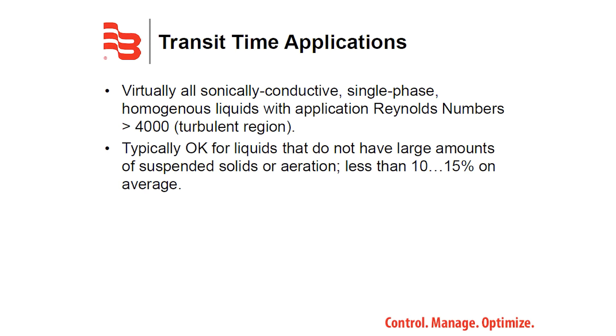Transit time applications require Reynolds numbers greater than 4,000. Transit time technologies are typically suitable for liquids that do not have large amounts of suspended solids or aeration — approximately less than 10 to 15 percent on average.